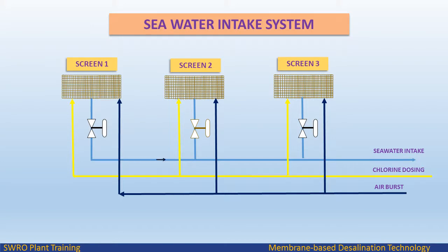Sea water supply to the RO plant is taken from a distance of about 600 to 800 meters offshore through submersible intake screens, which are connected to the main intake pipeline. Screens with a slot clearance of 3 millimeters are installed — 3 intake screens A, B, and C, each at 50% capacity. An airburst pipeline and chlorine dosing pipeline are connected to each screen.